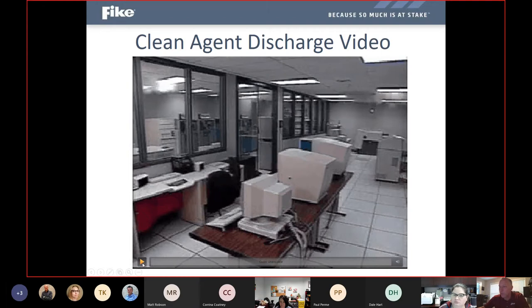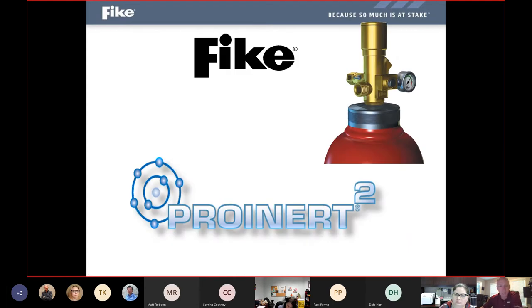So while the agent itself is not hazardous or toxic for anybody that might be in the room, one of the main reasons we recommend that everybody leave the room before the system goes off is that as soon as you open a door, the agent is going to leak out. And now you've reduced your concentration and your design effectiveness of the system. It's also going to be very hard to see your way across the room because there is going to be an initial fog, just because of the temperature differential that the agent introduces, making it more difficult to see a clear and safe passageway to the exit. So I apologize that the video is not playing for some reason there. But that's just to give you an idea of how those clean agent systems work and why they're so popular.